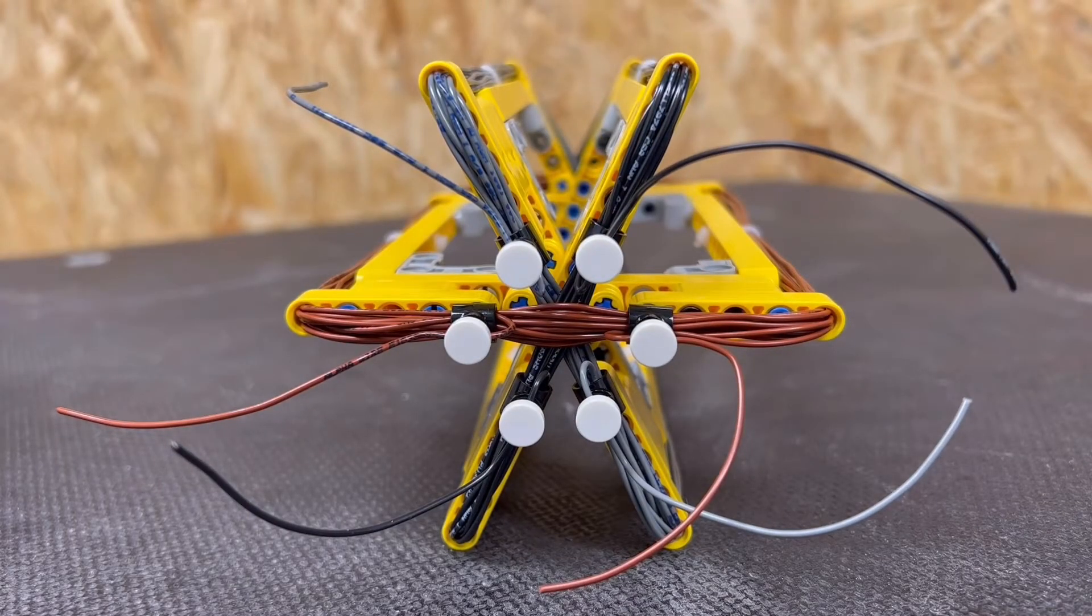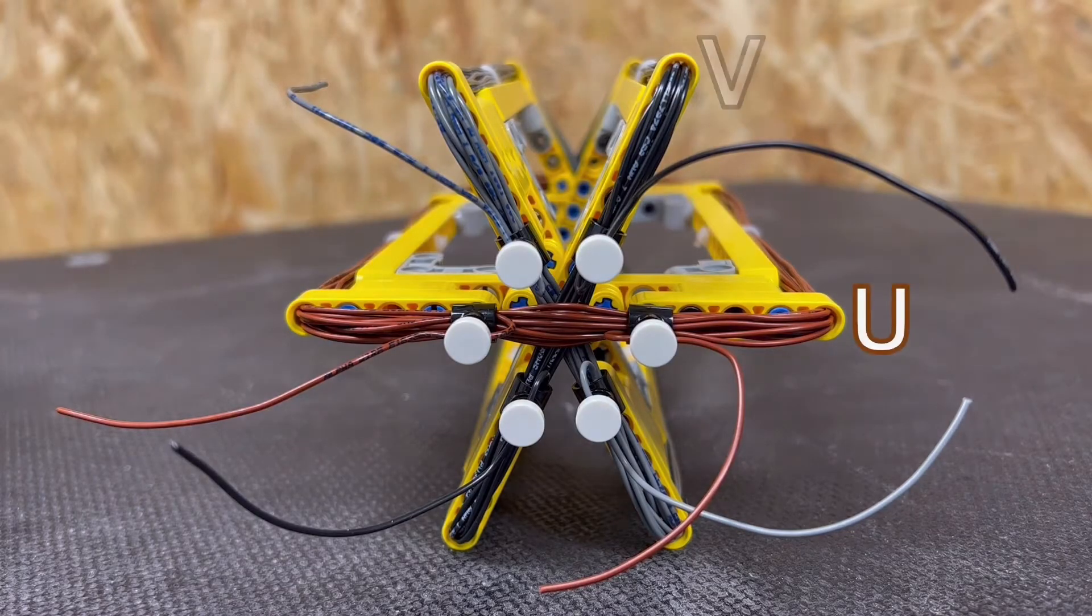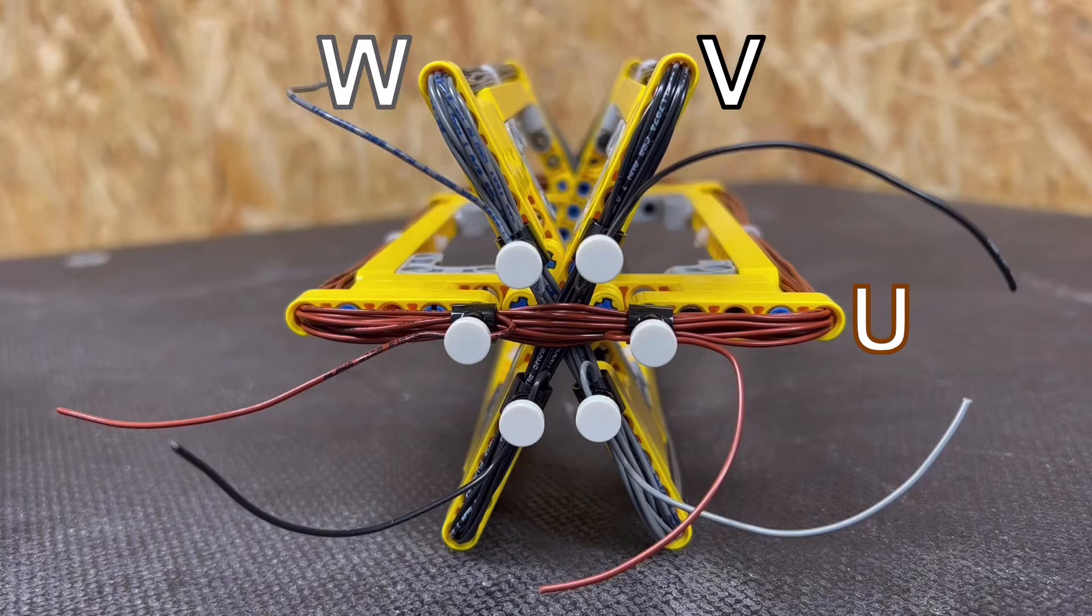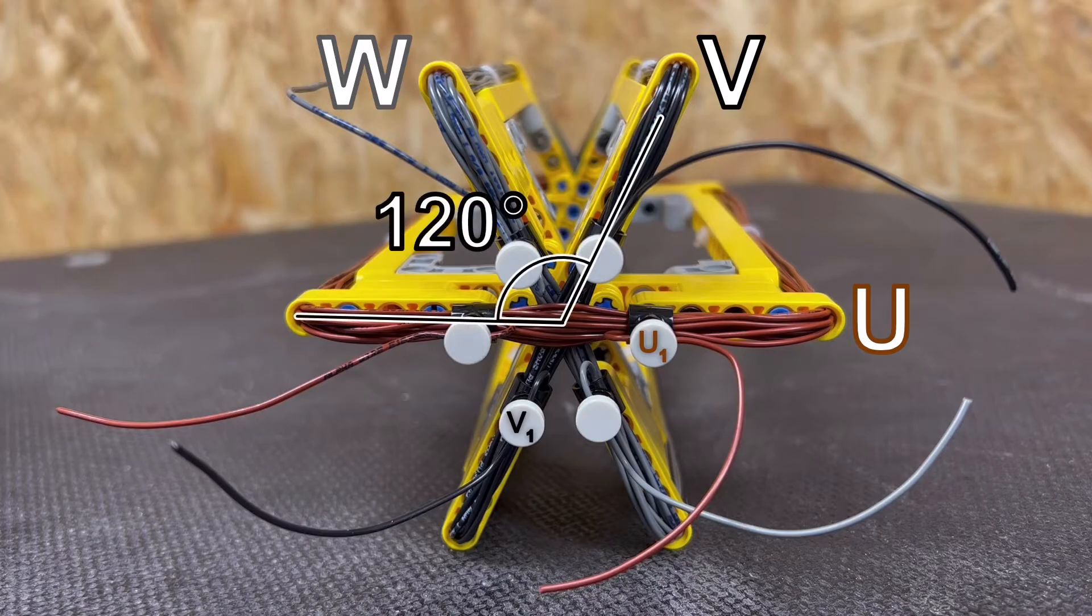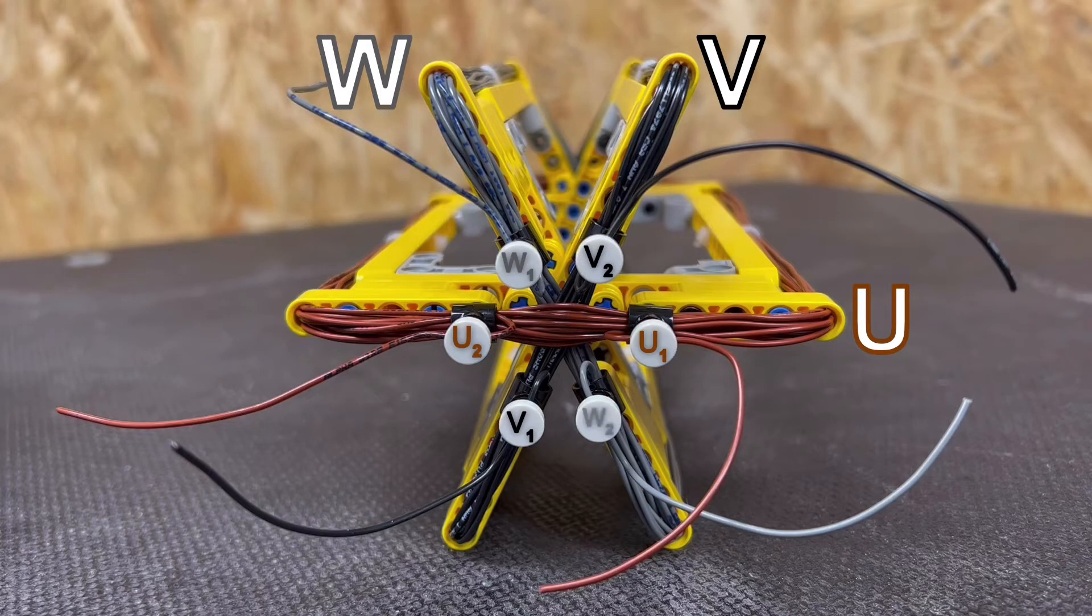Although these are connected to an AC supply, it's helpful to know which end of the winding is which. To start with, depending on where you are in the world, the markings on these conductors will be a little different. But here we're going to go with U, V, and W, and we'll differentiate the two ends of each winding with numbers. So this one here is U1 and the other end is U2. This end will be V1. Notice that the end is offset by 120 degrees from U1, and the other end V2 is offset by 120 degrees from U2.